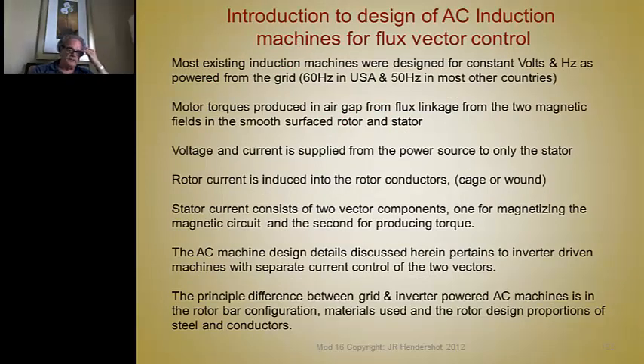And that leads me to the most important point of this whole lecture: the existing induction motors we find out there on distributor shelves, the ones we're most accustomed to, had an original design criterion, when they were first conceived, based on the assumption that they're always going to be powered with a constant AC voltage at some frequency. Now we have voltage standards and frequency standards in about every country. In the United States, the frequency standard is 60 hertz. In Europe and much of the rest of the world, it's 50 hertz.